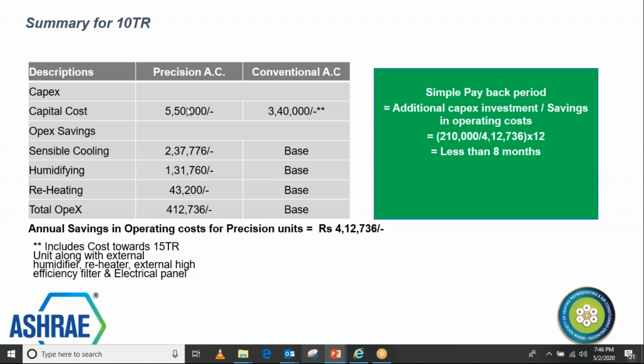So obviously the initial cost for the precision AC is higher compared to comfort, because each component installed in the precision AC is designed for a different life, for different hours to operate, and different efficiency levels which are much better compared to the comfort system. So its initial cost is obviously high. When you add the operational cost, comparing this system which we discussed in the last slides, this is the cost which was coming because of the sensible cooling impact, because of the humidification, the dehumidification, and the reheating. So 4,12,000 is lost because of the comfort system extra on these 3 components, and this is the saving in precision AC. When you add this together as a saving in precision AC, you can see on the right side that your ROI, your payback, is less than 8 months.